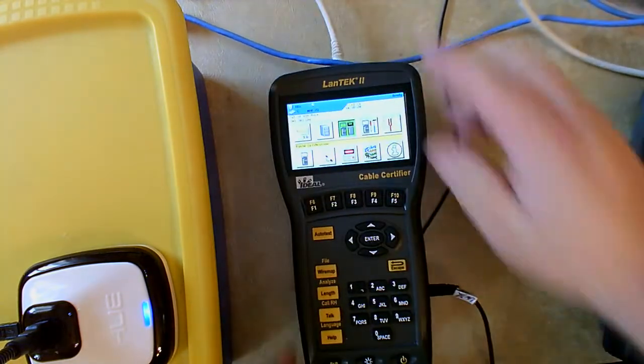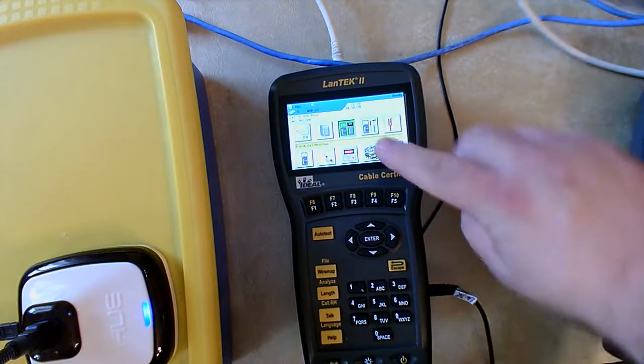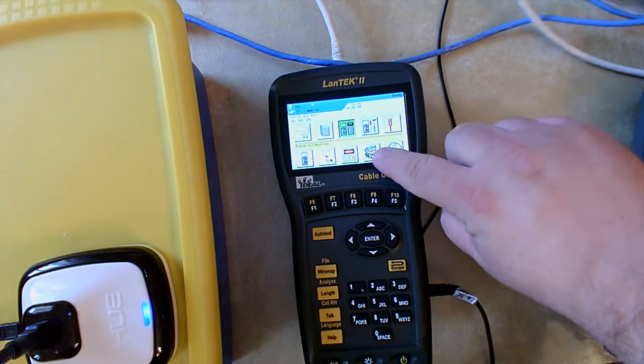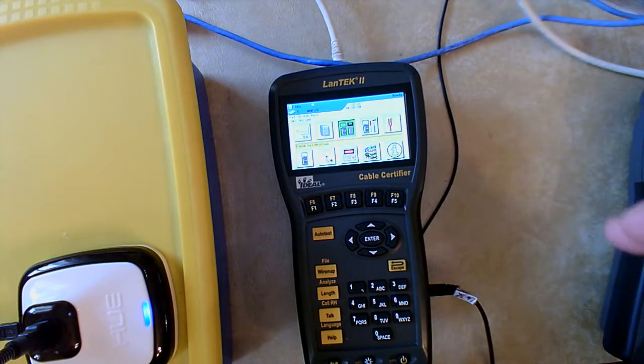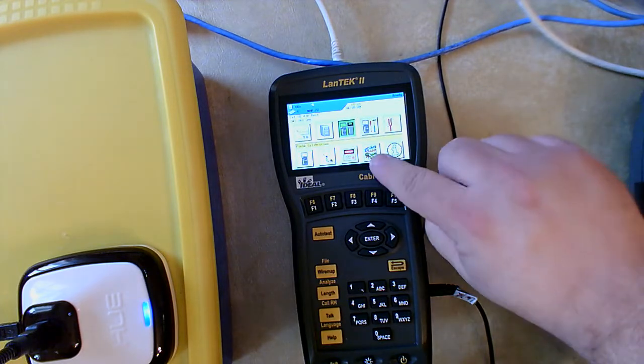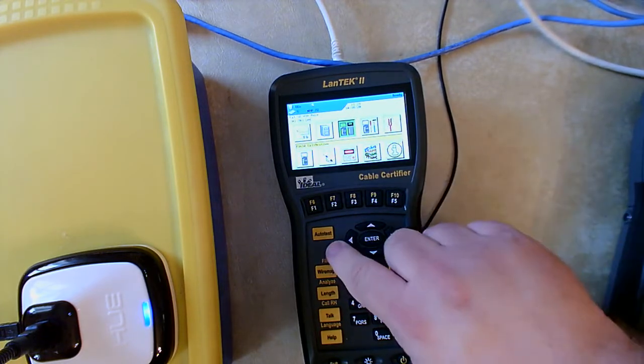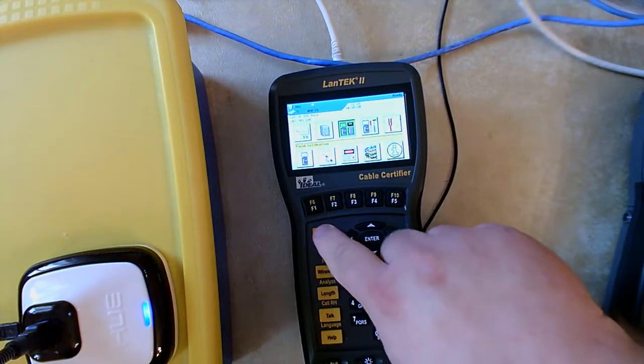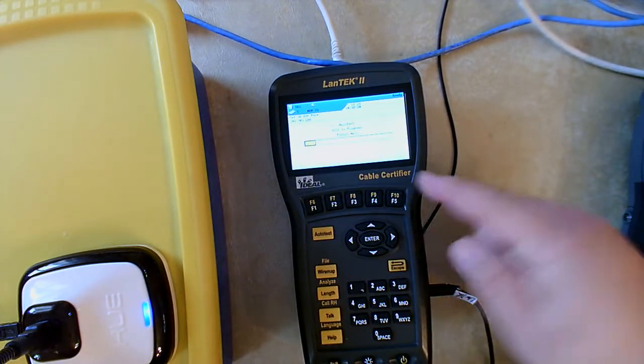What I need to do now is, since I set all the parameters of please use permanent link, TIA 568 permanent link 5E test, it knows what tests to run. So if I hit auto test, it's going to go through that series of tests.